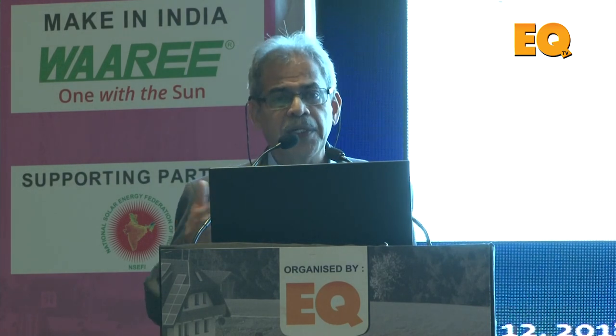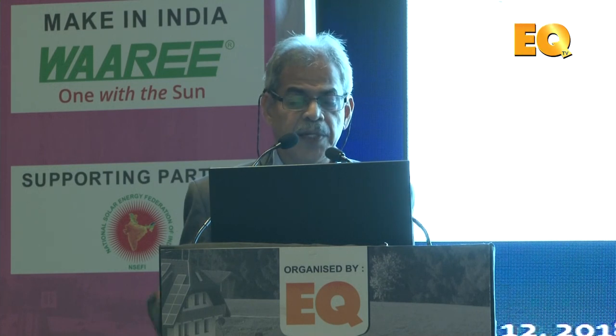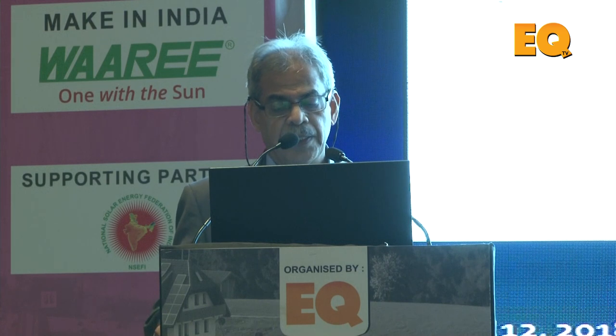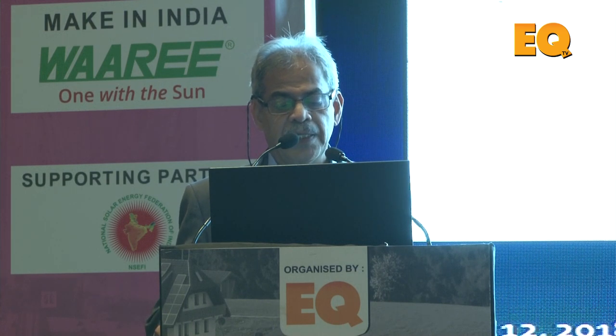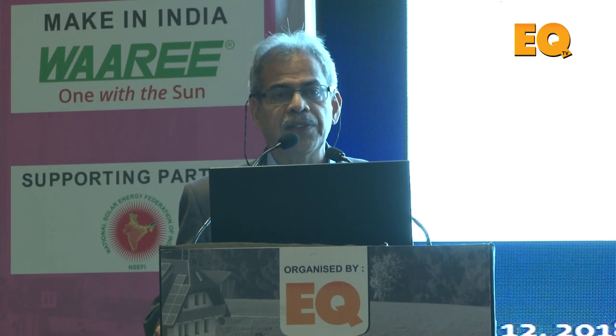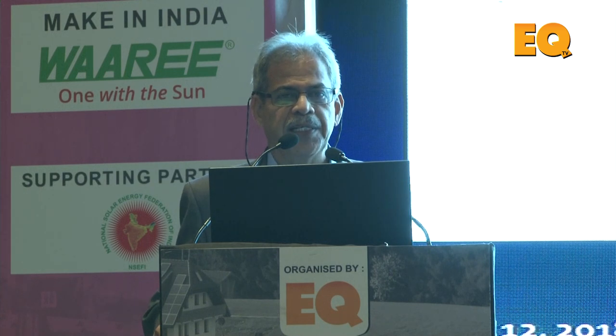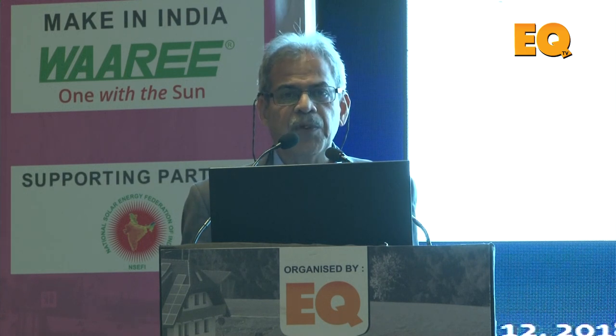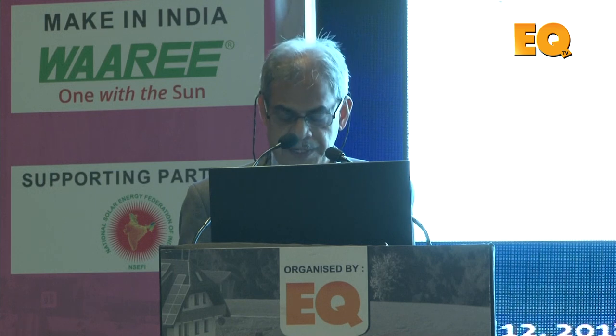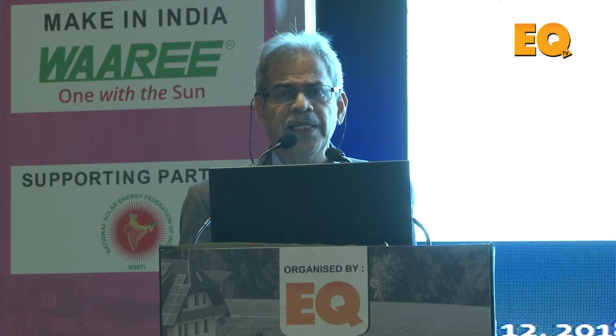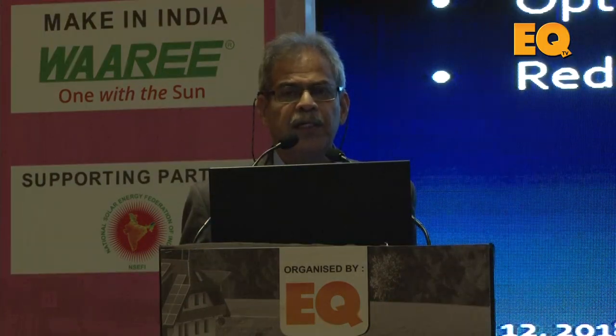Then you can even dig deeper. This is looking at daily generation loss, and you'll find that during 9 and 10 a.m., one of the inverters is actually losing some power, losing some output, and that could be due to shading or any other effect. So these are the things that need to be monitored.